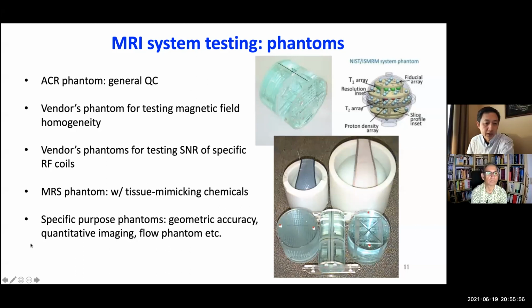And we have the quantitative imaging phantom. Here I'm showing a phantom recently developed by NIST and ISMRM. You can see they are T1 arrays, T2 arrays. So those phantoms allow measuring the accuracy of T1 measurement, T2 measurement, and other quantitative imaging. And also there can be flow phantoms or perfusion phantoms, different special purpose phantoms.